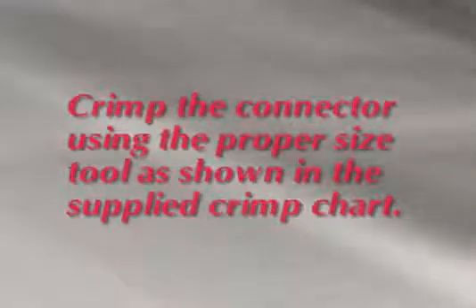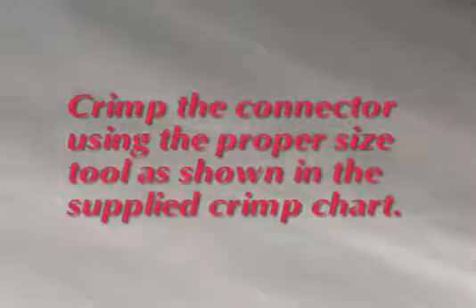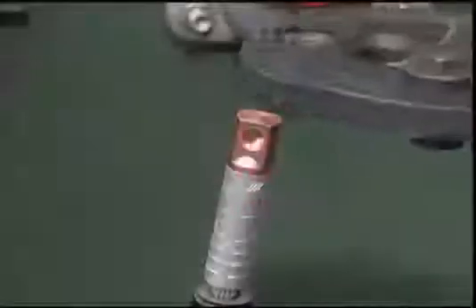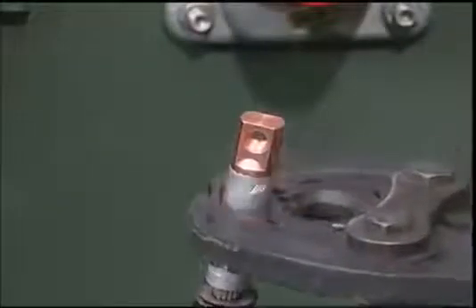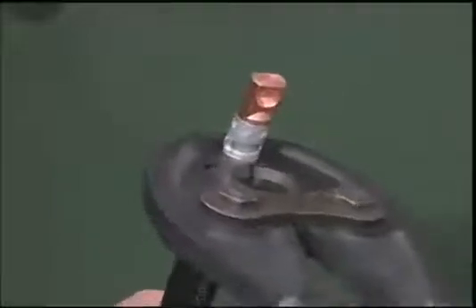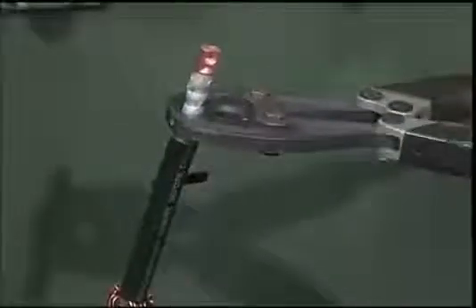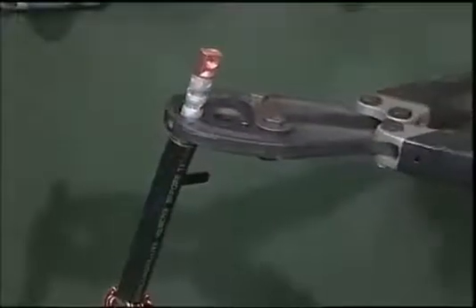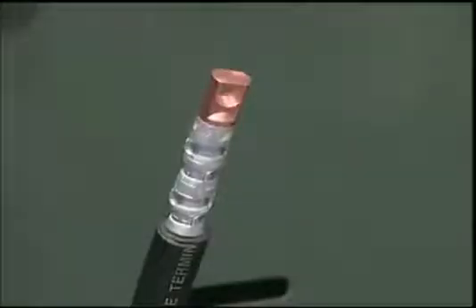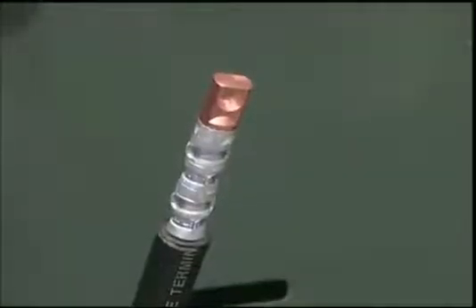Crimp the connector using the proper size tool as shown in the supplied crimp chart. Start the first crimp just below the knurl at the top of the crimp barrel. Rotate the tool 90 degrees for each successive crimp. Place the number of crimps as shown in the crimp chart. Be careful not to overlap the crimps.